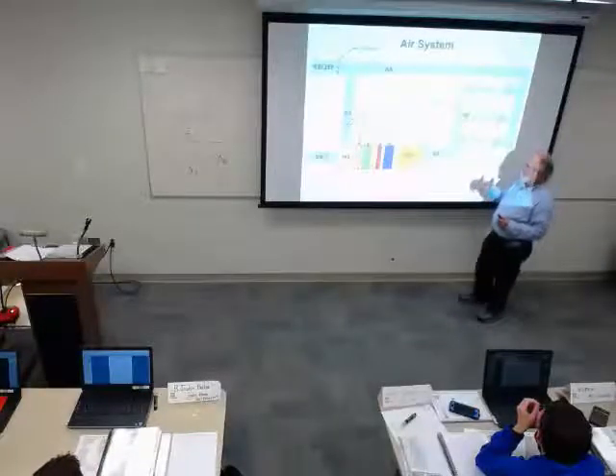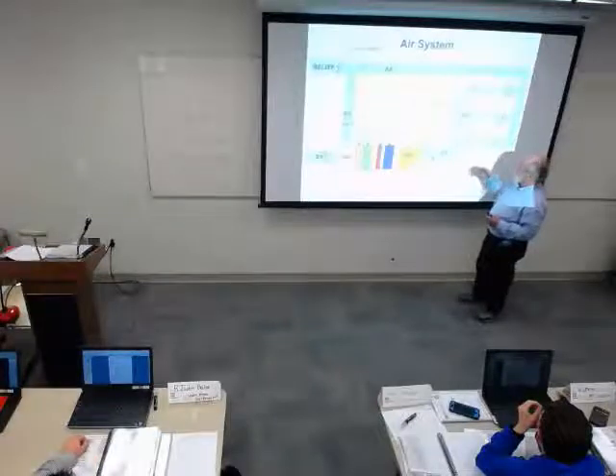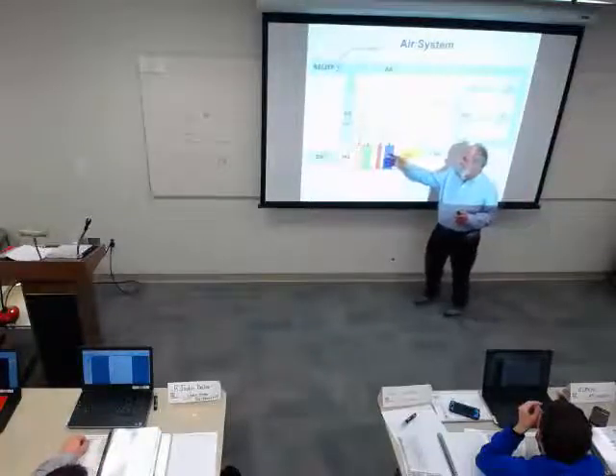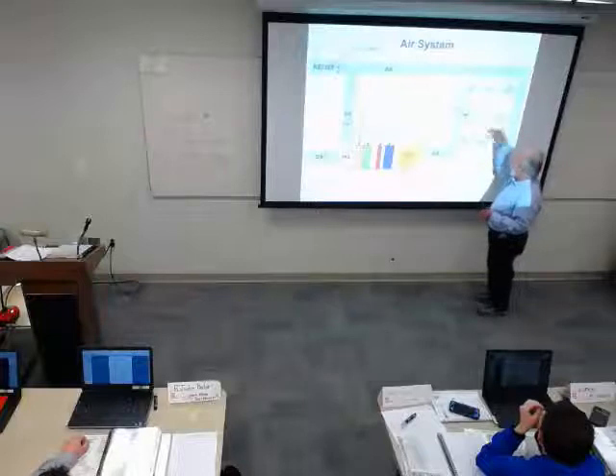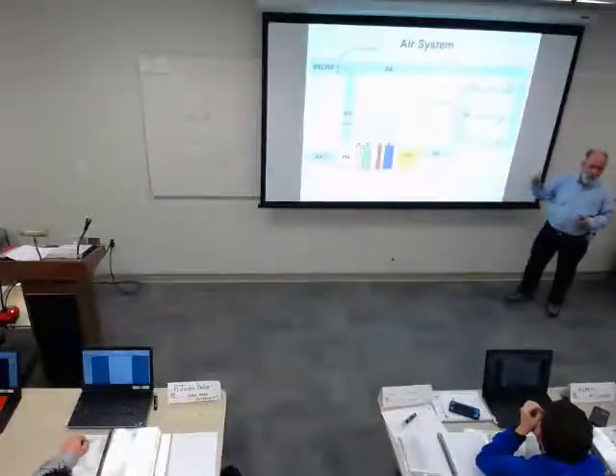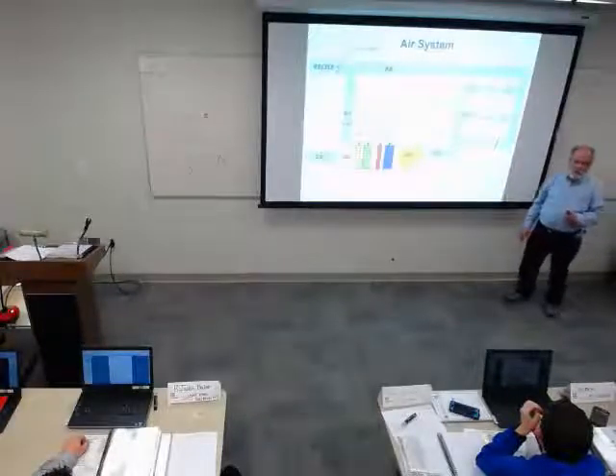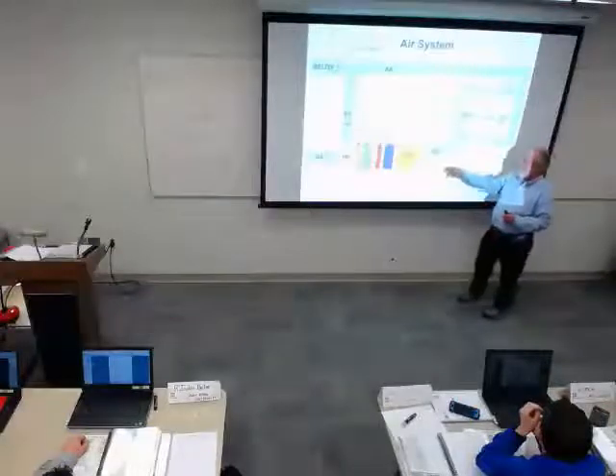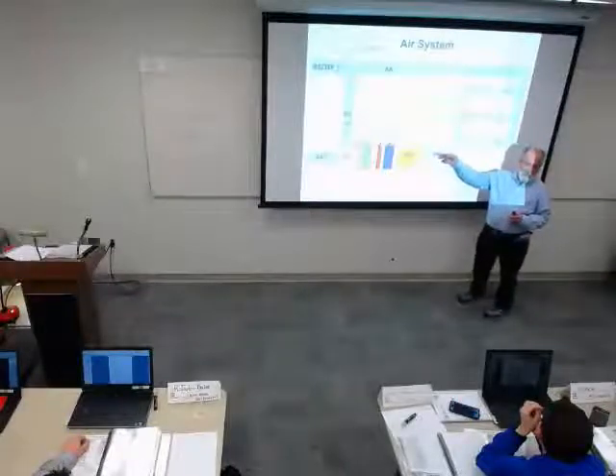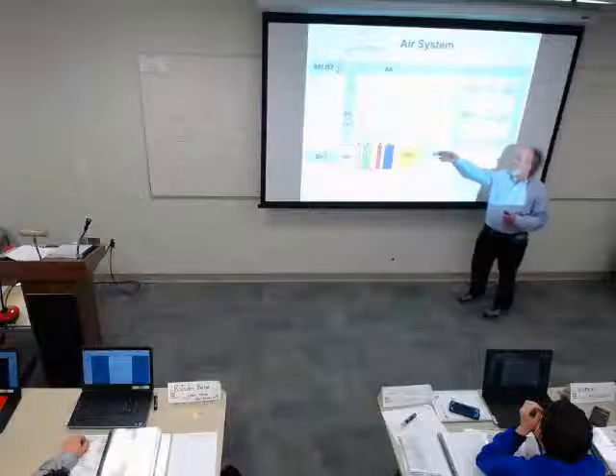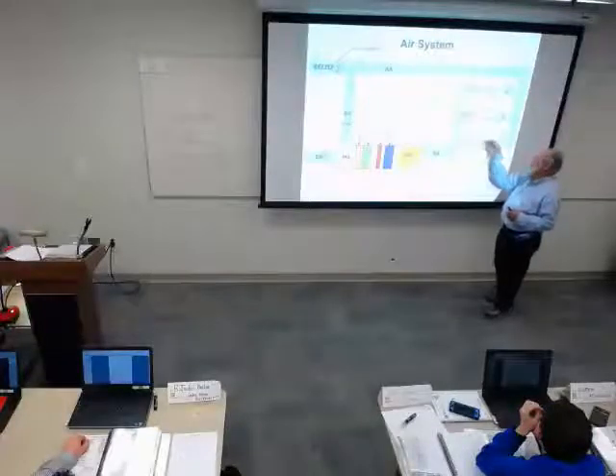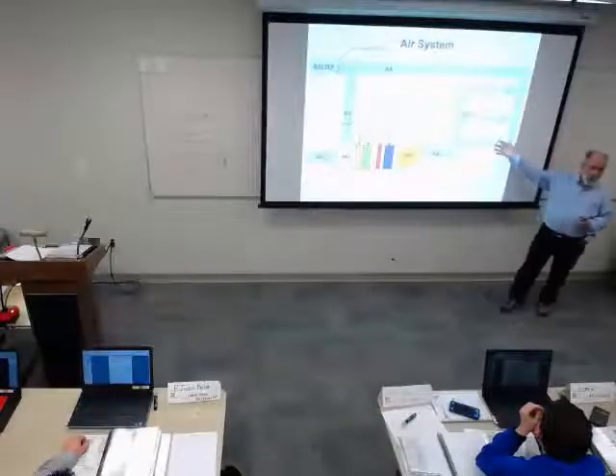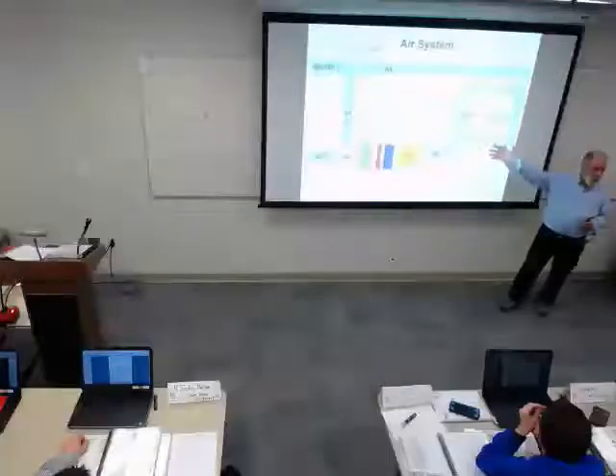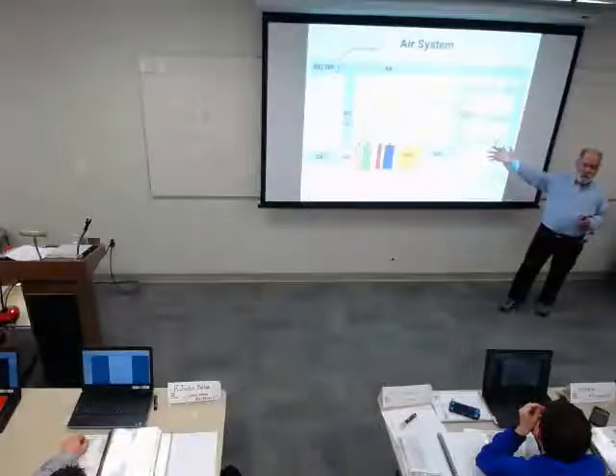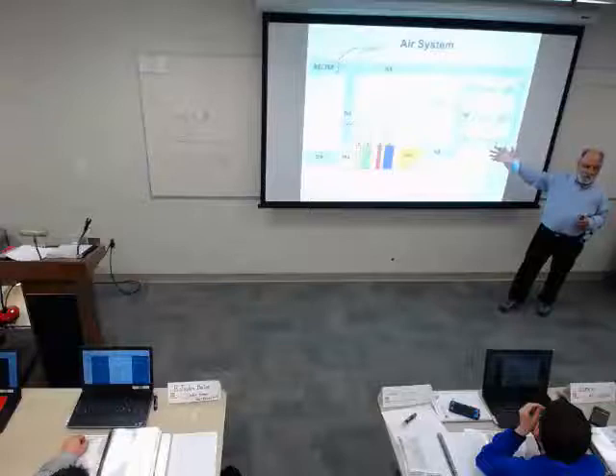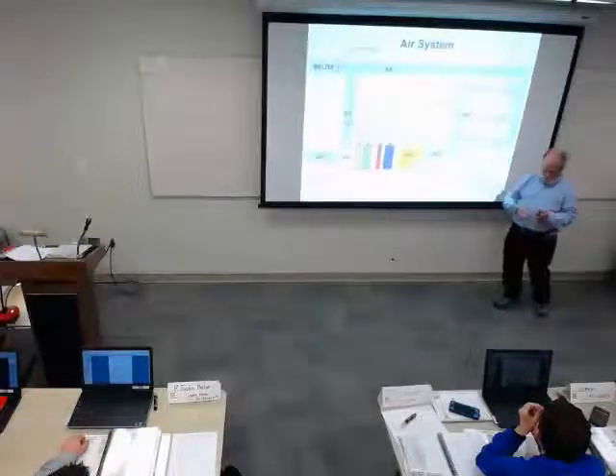For a constant volume system, things get a little bit crazier because it'll reset these temperatures, hoping that these zones always have the same kind of loads. And it doesn't always work so well. On a constant volume system, we change the supply air temperature. In a VAV system, we hold that constant, and then we change the airflow through the space. So we're seeing more of these, unless you've got a small, one-zone unit, and then you'll see constant volume. But otherwise, we do the varying here.